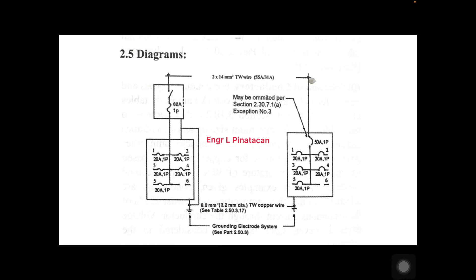The single line diagram shows 2×14 mm² TW wires, rated at 55 amperes over the 31-ampere load. We have a 60-ampere, one-pole main breaker with 5 branch circuit breakers and 5 branches of fuses. Circuit 1 through 5 are each 20 amperes, one pole. Circuit 6 is a spare space, consistent with our example of not more than 6 circuits.